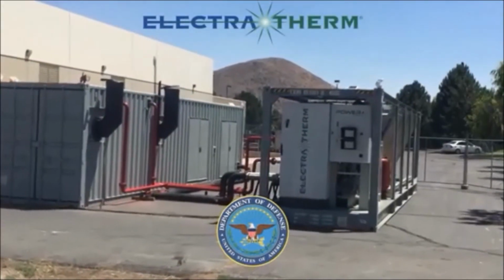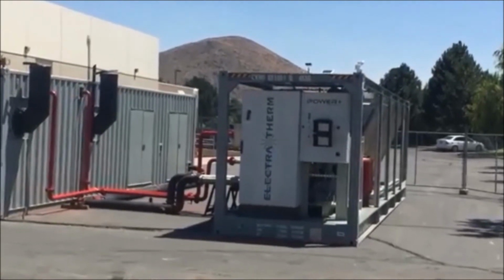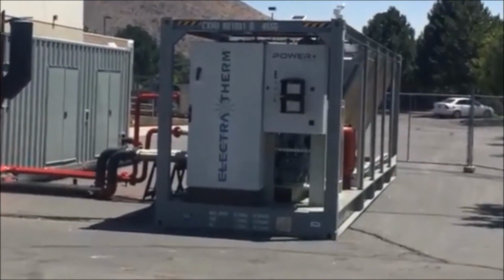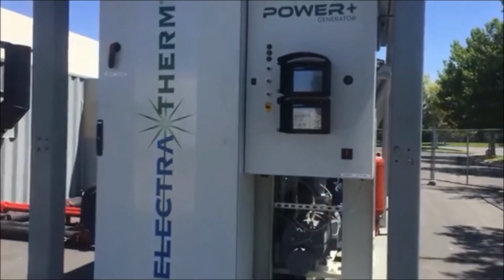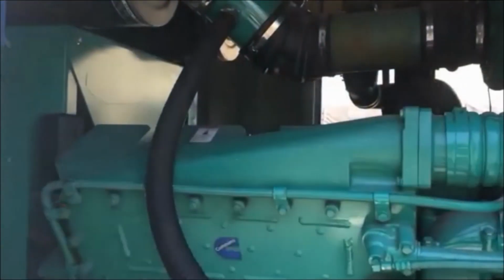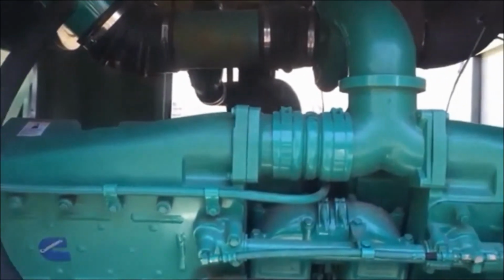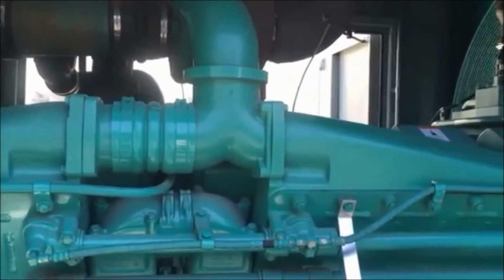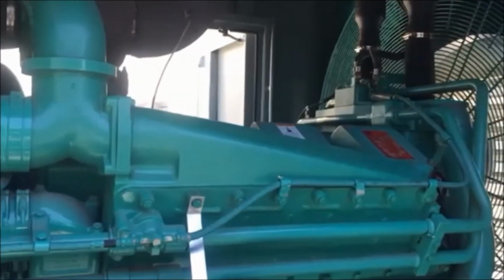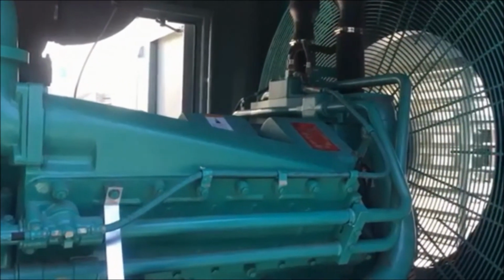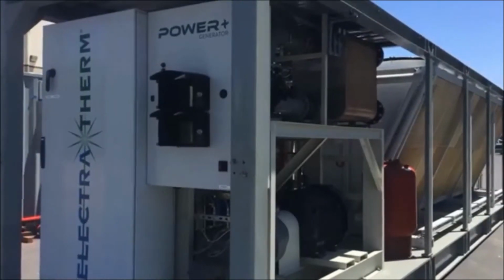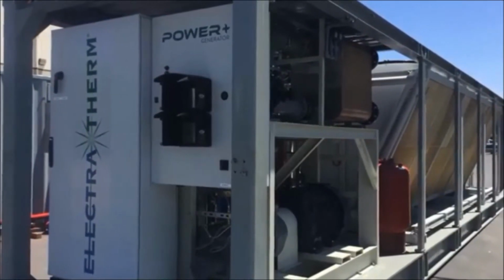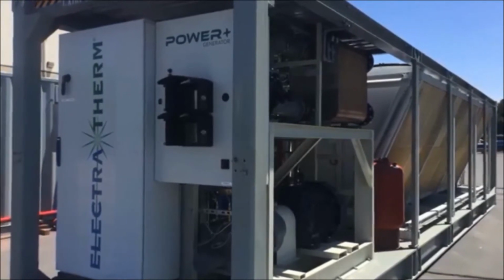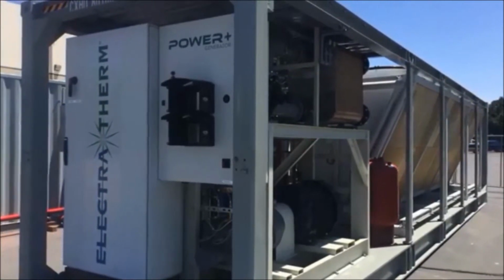ElectraTherm and the U.S. Department of Defense have commissioned the first fully integrated stationary engine and waste heat-to-power generator. ElectraTherm's Power Plus generator was integrated with a Cummins 1.1 megawatt, 1,500 horsepower engine to increase fuel efficiency and eliminate the cooling load on the engine by replacing the engine's radiator entirely. The Power Plus generator displaces the radiator's capital cost and parasitic load, generating additional power and marking the first radiator with a payback.